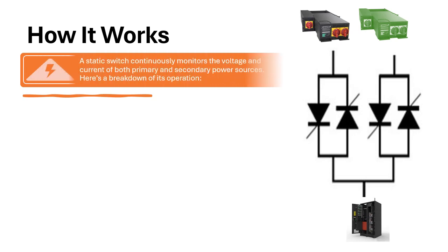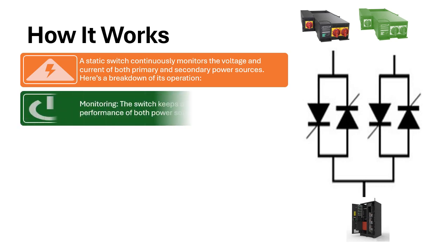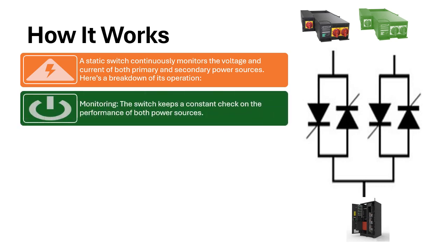How it works: A static switch continuously monitors the voltage and current of both primary and secondary power sources. Here is a breakdown of its operation. Monitoring: The switch keeps a constant check on the performance of both power sources.